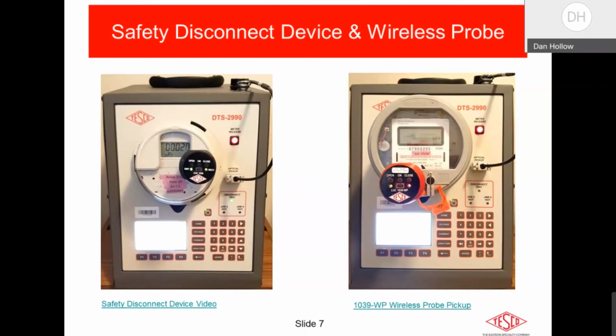So if you're trying to communicate with a meter and you're only seeing one of those LEDs flashing, that means that commands are coming out from the meter manufacturer software, or the software being used on the laptop or desktop, and it is being seen by the probe, but you're not getting any responses from the meter. The meter is not responding to the commands being sent to it, so you're not getting any received information from that meter. So having those LEDs is very helpful.